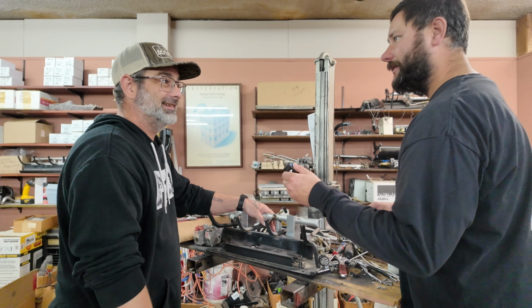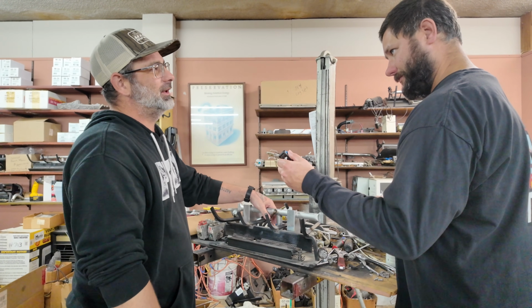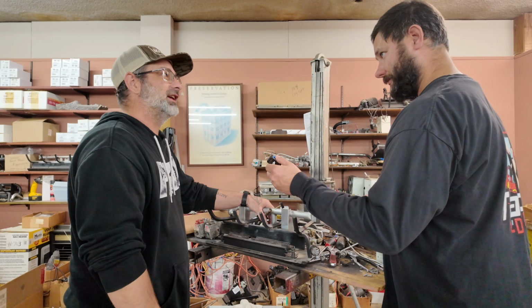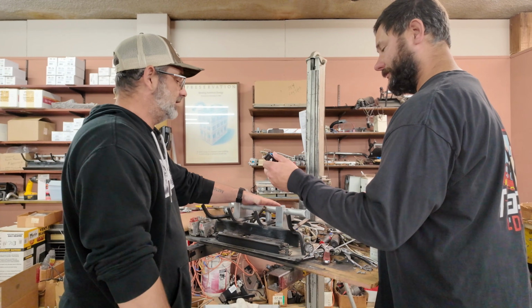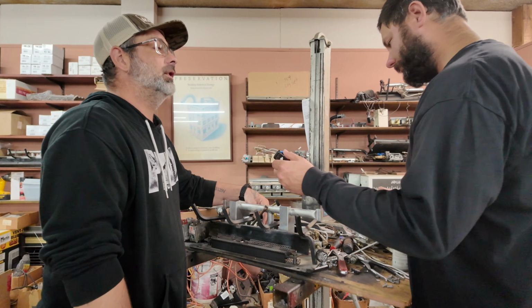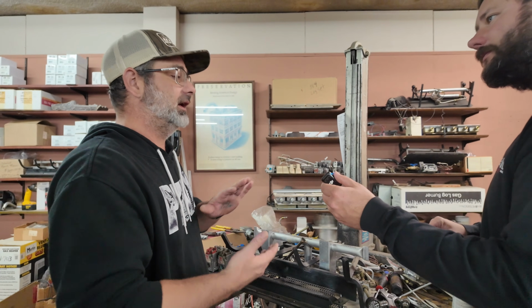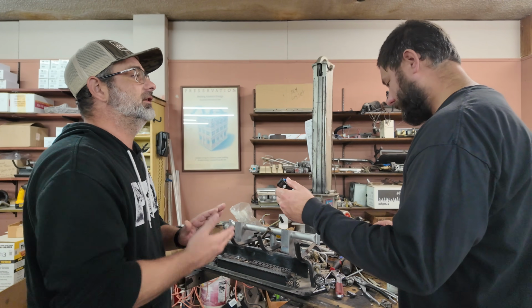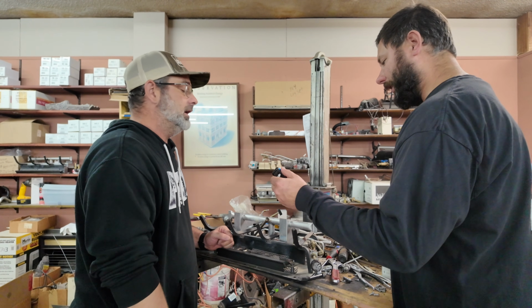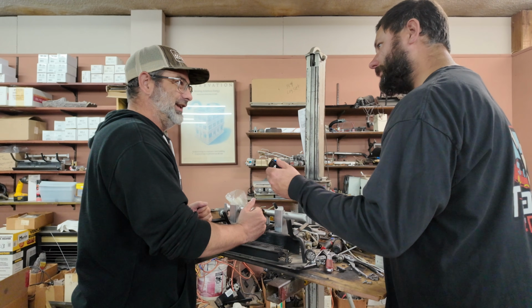If it stays lit for 5 minutes, 10 minutes, 20 minutes, and then goes out, that typically means they need to have it serviced and cleaned out. The oxygen sensor on it, or the ODS sensor they like to call it, it gets stopped up full of dust. It doesn't breathe right, and then what happens is, because it's not hitting the thermocouple like it should, it's shutting itself down as a safety mechanism. Got it. Nothing's wrong with the burner itself, besides that good old-fashioned cleaning.